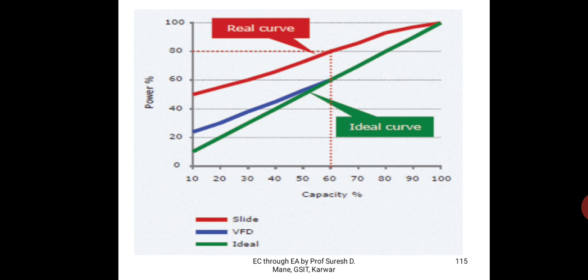Red line, real curve. But with VFD, 30% capacity is consuming 40% power, and 10% is consuming only 25% power. You understood? Especially at 60% and below, you will find a remarkable difference. Even below 80% you can see the difference between the real power and the VFD drive power. So variable frequency drives consume less power even at part loads, right from 10, 20, 30%. So you can vary the power requirement. This is why inverter AC and inverter lifts are very popular now, because they use less power.